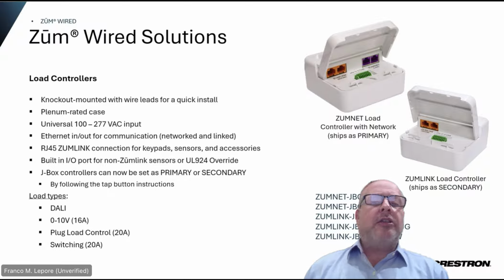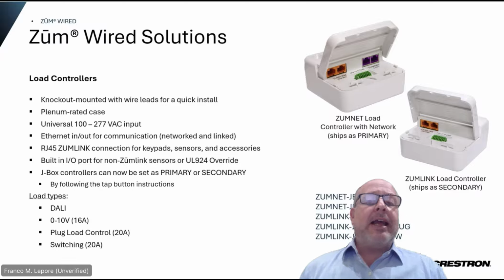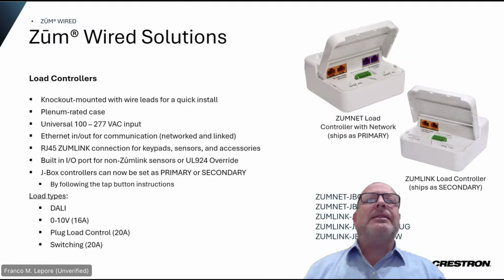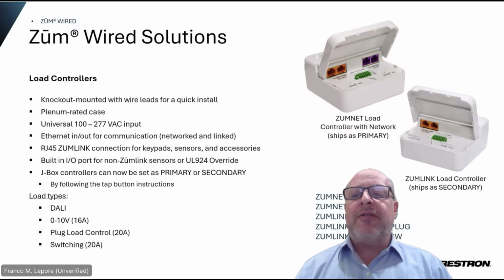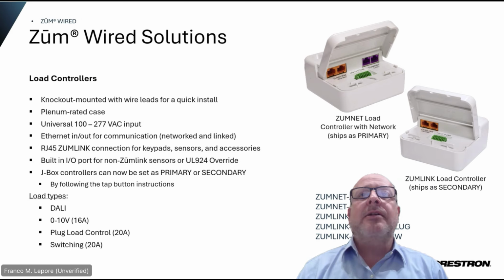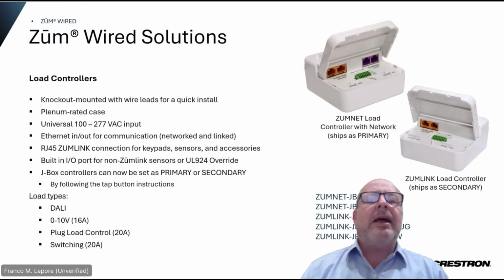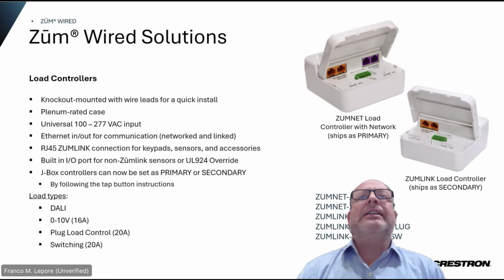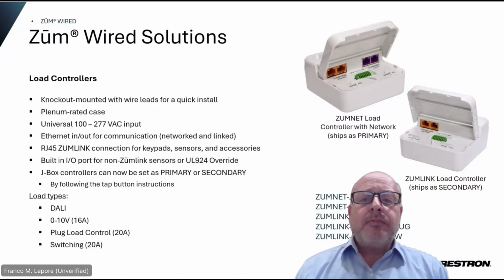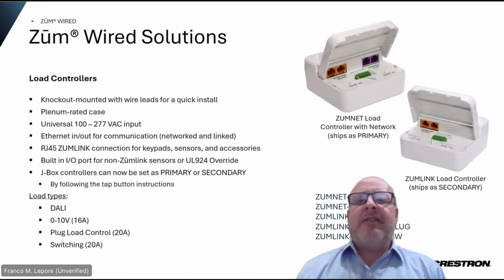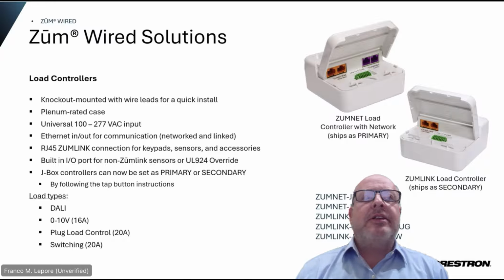And the reason there's two there is because of what I mentioned earlier—I can take one Ethernet or network connection from one of my network switches, and then cascade or daisy chain up to 20 different spaces, having up to 32 different devices in each of the spaces. That could be sensors, keypads, and there's a lot of other things built into the wired product as well. Most importantly, you have the CTs that are included in it, but you also have a device that's integral into every single one of our wired components called a SIM, short for sensor integration module.